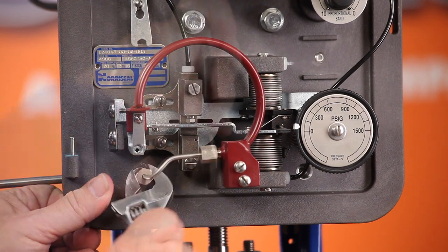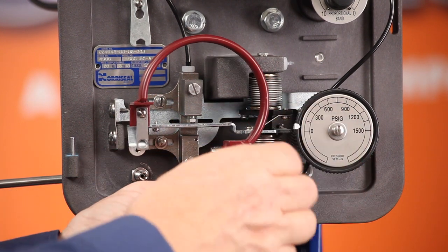Remove the control tubing and the two screws that hold the Bourdon tube to the mounting base. Make sure you keep the link and bearing to use with the replacement Bourdon tube.